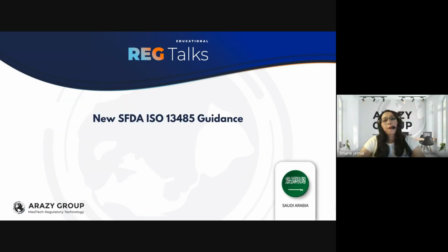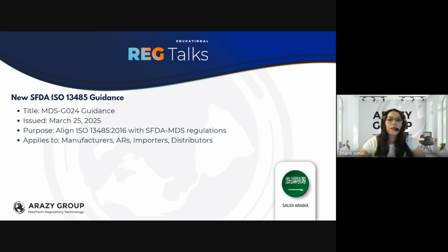In Saudi Arabia, the update is regarding the new SFDA ISO 13485 guidance. The authority has issued this guidance, known as MDS-G024. This is basically to align the ISO 13485:2016 quality management system with the SFDA medical device sector in Saudi Arabia.